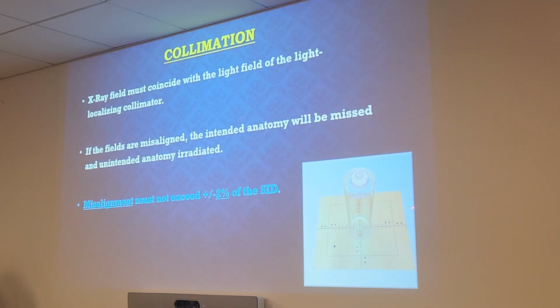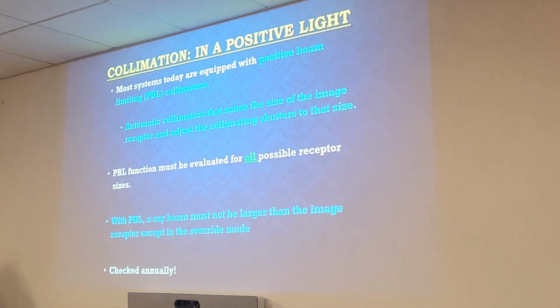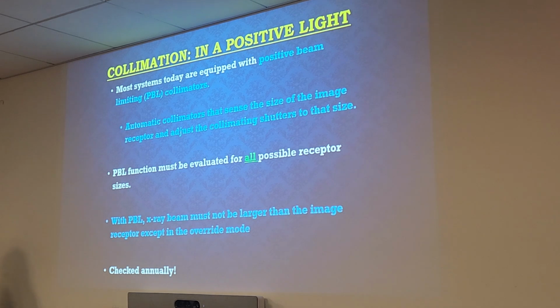This right here is your plus or minus, the ones inside of the box. So if your collimator is ranging outside where these dots are, then that means it's misaligned, and they have to adjust the collimation. So with these boxes, you have a negative side and you have a positive side. So the circles that are within each of these boxes, you cannot go outside of that. Your plus or minus 2%. Okay? I did have a video, but that's too much to go through and we're moving on. I'm trying to save time.